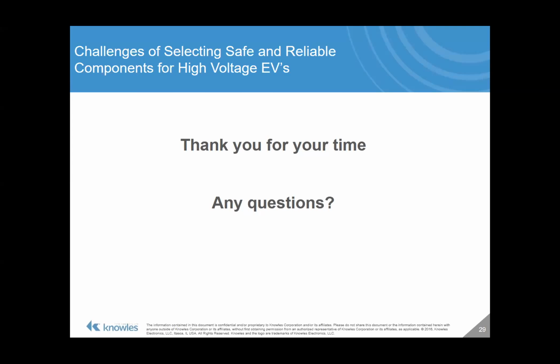Actually, I just have another one come in. Field testing for isolation, we couldn't use 500 volt. Will 1000 volt be enough to check loss of isolation testing on the 800 volt systems? I think the answer I've got to give there is go back to the specifications and see what you need to meet. Our specifications as component suppliers are being given to us by our customers, by you guys who are working out what you need to do. And I would say 1000 volts to check for loss of isolation on an 800 volt system is very much lower than I'm normally seeing.